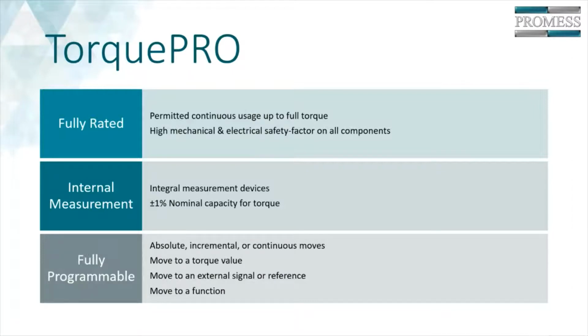It's fully programmable. Some of the program options include move to a position, meaning the Torque Pro can move a specified amount, set as rotations, degrees, or even relative values based on other program functions. The Torque Pro also has the ability to move to a specified torque value, which we call a move to signal. The move to signal can also be used to move to any external sensor value, such as a digital probe or flow sensor in a valve type check. It also has the ability to move to or home to an external proximity switch.